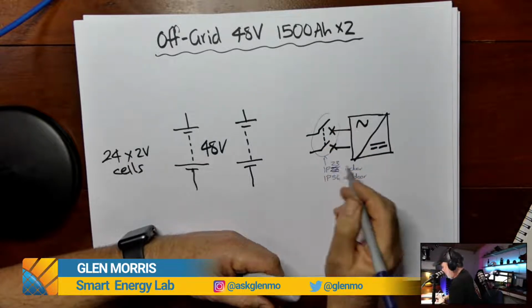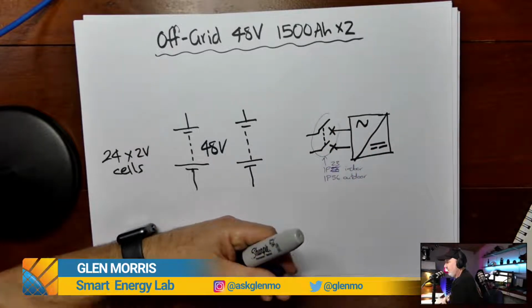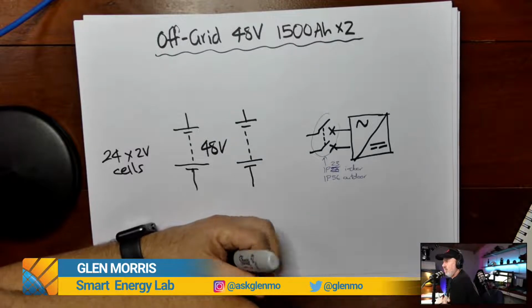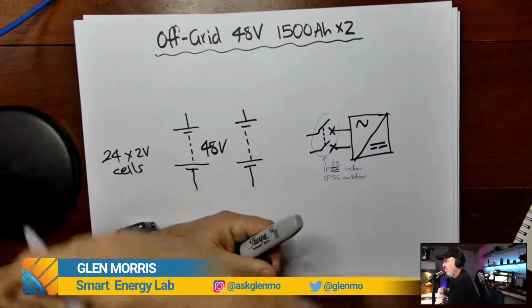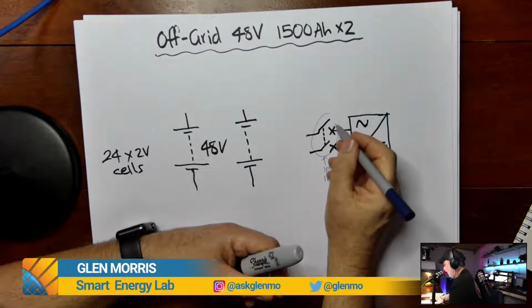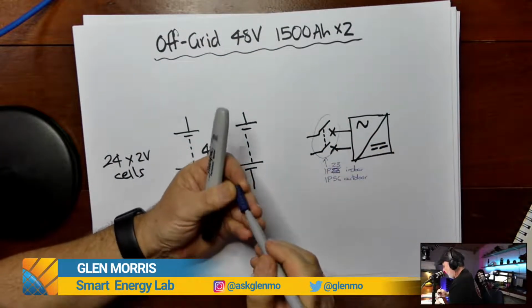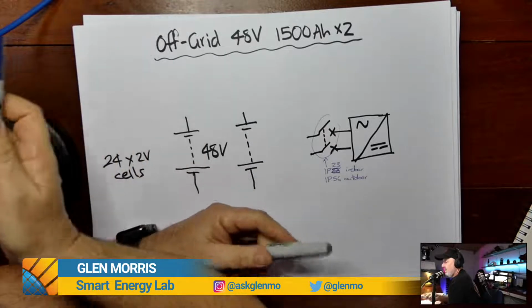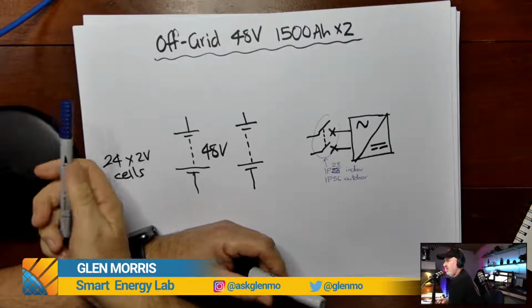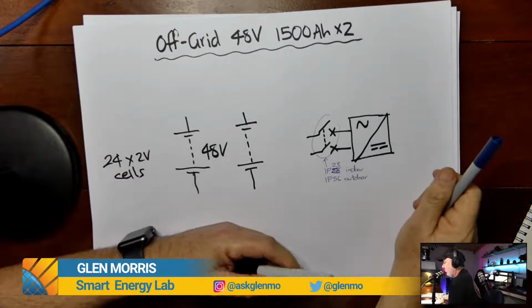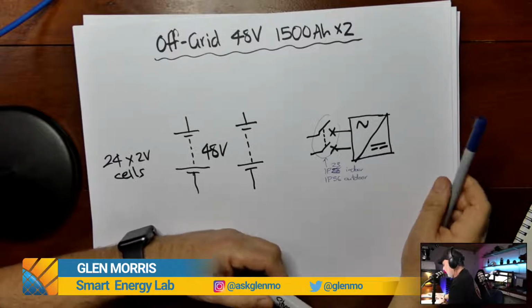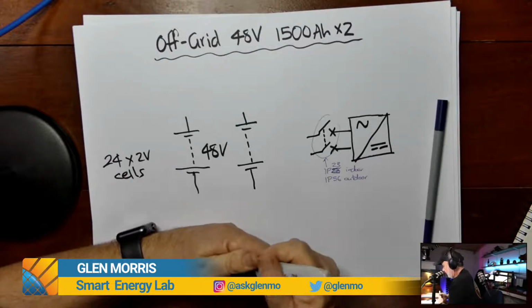Now, IP23 is hard to achieve with an HRC fuse switch. You should check with the manufacturer if it is actually IP23. So you may need to choose another product, or as many installers are doing these days, use a suitably rated circuit breaker, because you can get some very high current DC circuit breakers for use in battery systems.